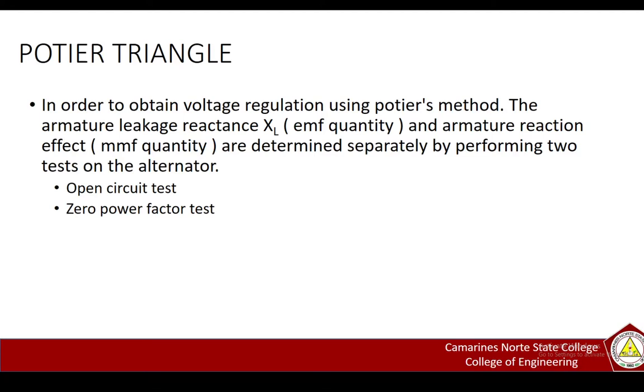In order to obtain the voltage regulation using Potier's method, the armature leakage reactance, which is an EMF quantity, and armature reaction effect, which is an MMF quantity, are determined separately by performing two tests on the alternator. Here is the open circuit test and zero power factor test.